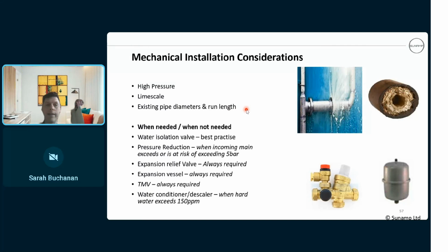We have had some jobs where there's no descaler and the customer's saying that the flow rate has gone down to a trickle, and that's because of the lime scale build up in our heat exchanger. It's just reduced it like a blocked artery, and that's down to installation defects really. And we talked about existing pipe runs and diameter and run lengths and stuff. But when it comes to components, water isolation valve, best practice, fit an isolation valve to the unit. I don't know why you wouldn't. Pressure reducing valve, if the pressure exceeds or you feel it's at risk of exceeding 5 bar, stick on a pressure reducing valve.